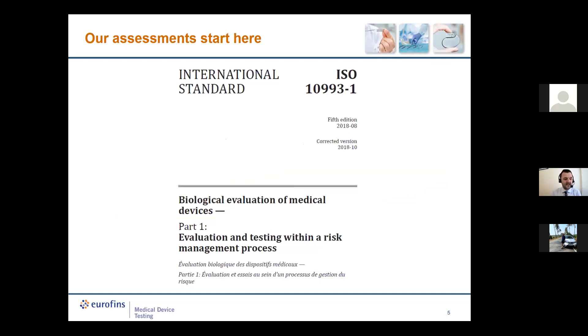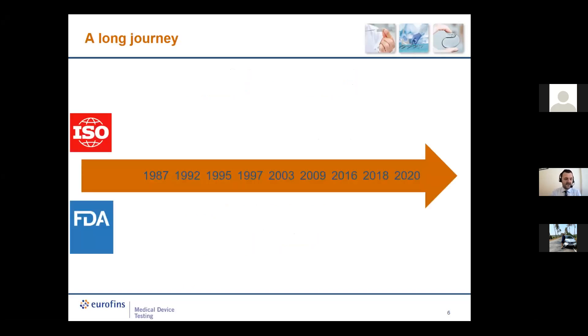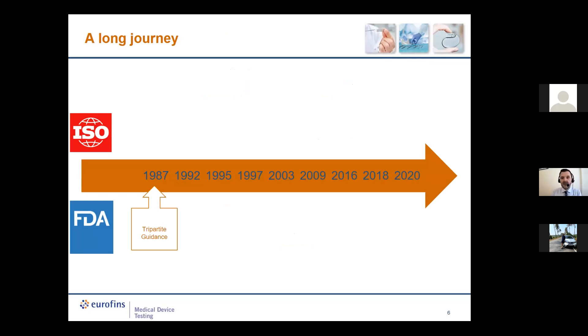The ISO 10993 series is the most important series for the biological evaluation, and when we start a biological evaluation we start from the beginning — ISO 10993-1 of 2018 — which is the first part both in publication and reading order for a complete evaluation. A little history: ISO and FDA played a sort of ping-pong in the biocompatibility field. In 1987, FDA issued the tripartite biocompatibility guidance G87-1, including several general principles ruling the biological evaluation. Those principles are still valid. ISO replied in 1992 with ISO 10993-1: guidance on selection of tests.